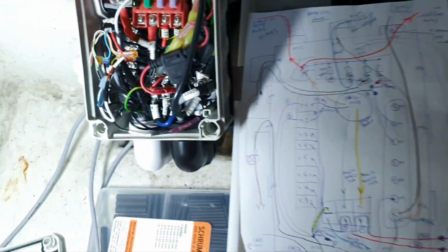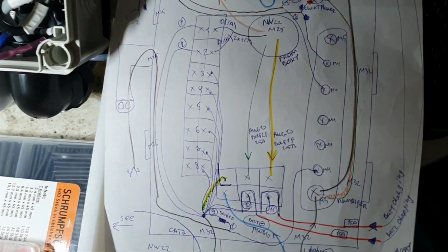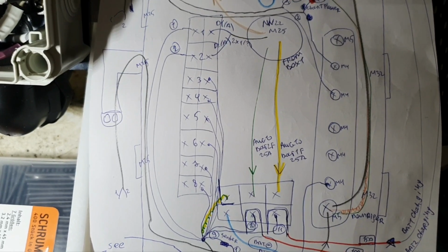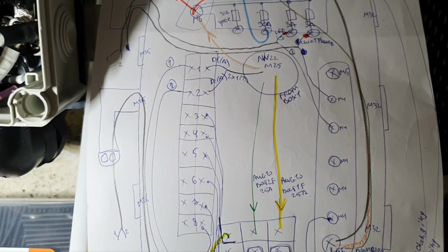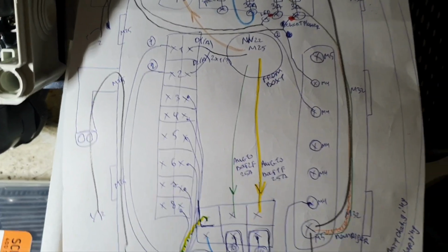Okay, then we provided 2 batteries that are fused there again with 25 ampere white fuses. I provided and take them by this bus for 12 volts. It comes here. I have here barrier terminal blocks, some spare from 3 to 8. 1 and 2 are used for monitoring the shunt circuit. I have a video about it. So here I provided batteries.